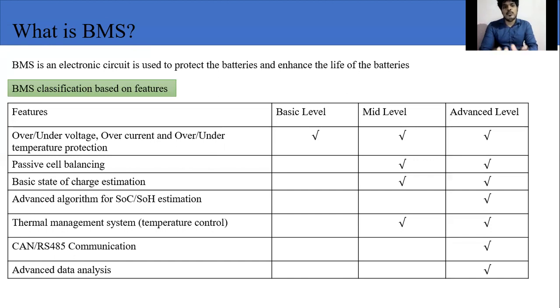According to that chemical composition, they have a different leakage current and a different self-discharge rate. That means one battery can be at 100% SOC level, another 98%, another 97%. Their voltage levels are also different. The maximum voltage level of a battery cell can be 4.2 volts, minimum voltage can be 2.7 volts, and for some batteries it is 2.3 volts.